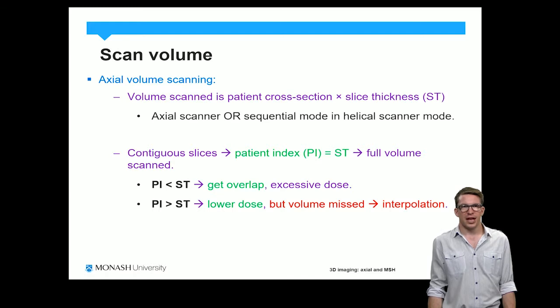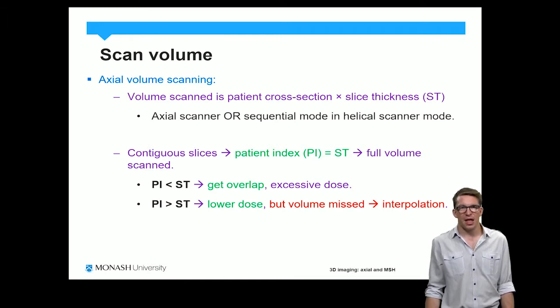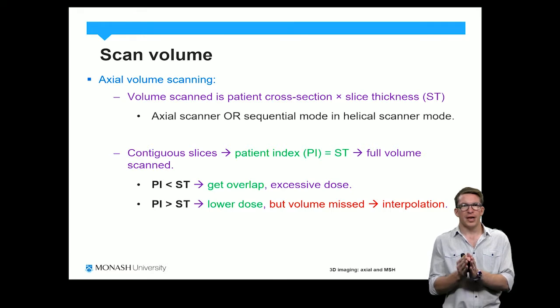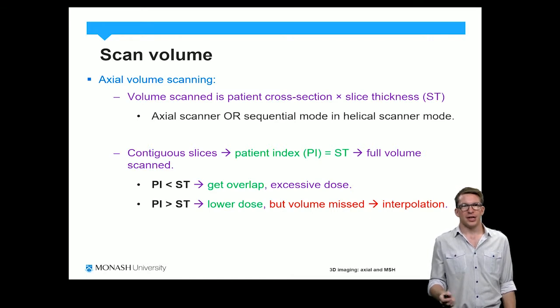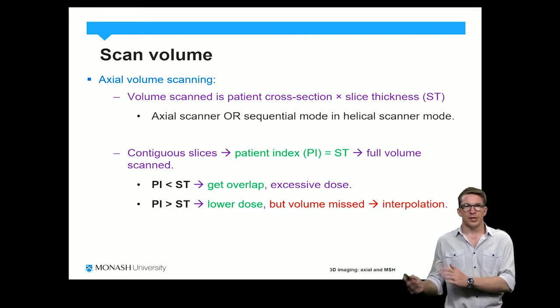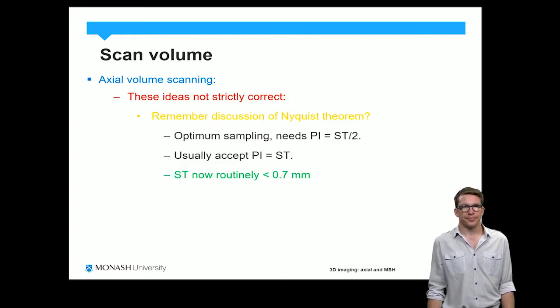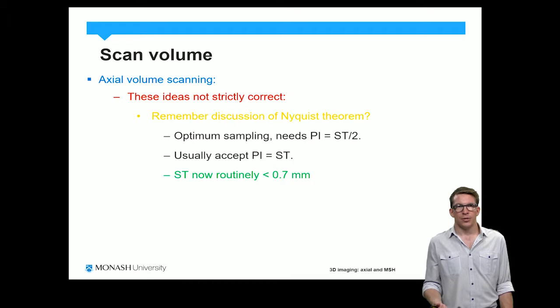In terms of the scan volume, in axial scanning we previously talked about a patient index. When our patient index is equal to our slice thickness, we have contiguous slices, meaning that the slices are all one after the other with no overlap. If our patient index is less than or greater than our slice thickness, we're either going to have overlap or we're going to need to do interpolation. To flesh this out mathematically in more detail, we can relate this back to the Nyquist theorem.